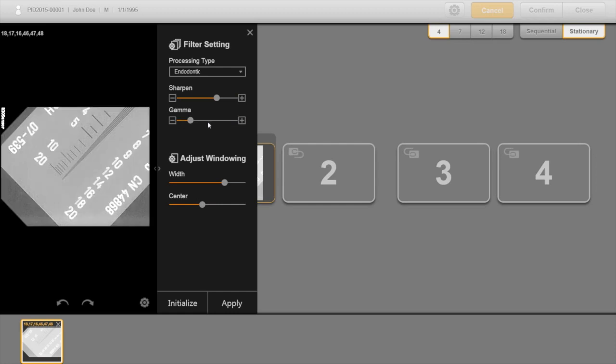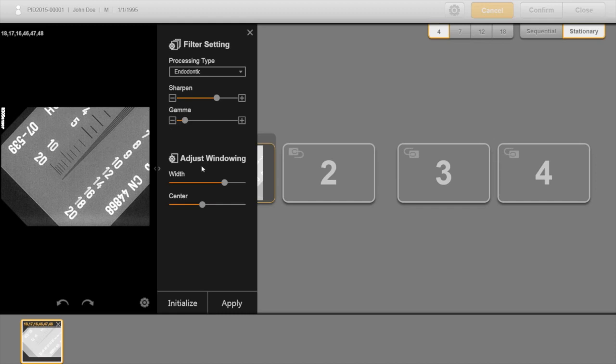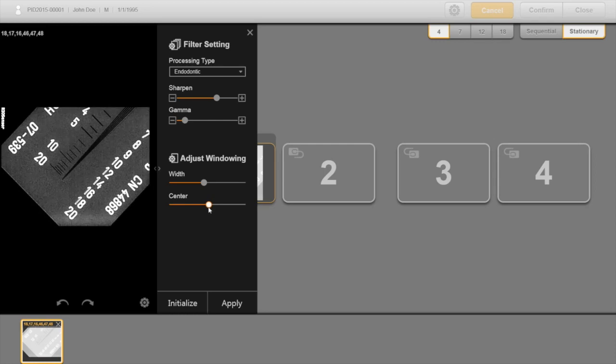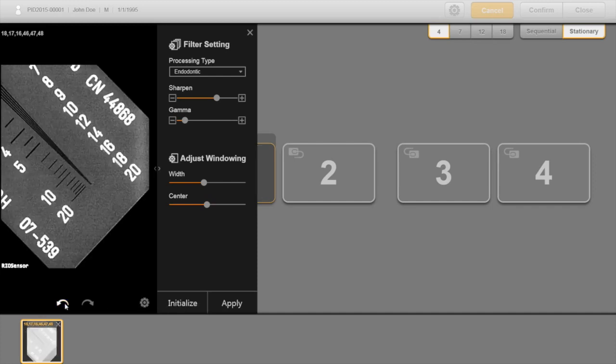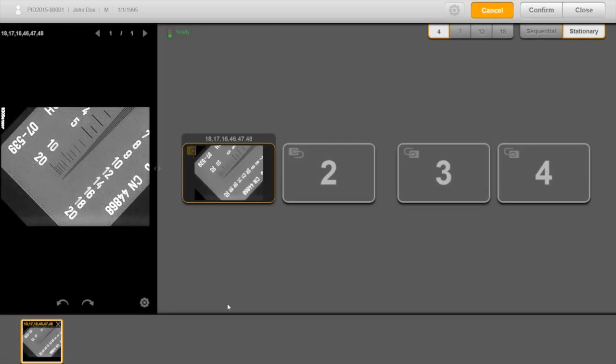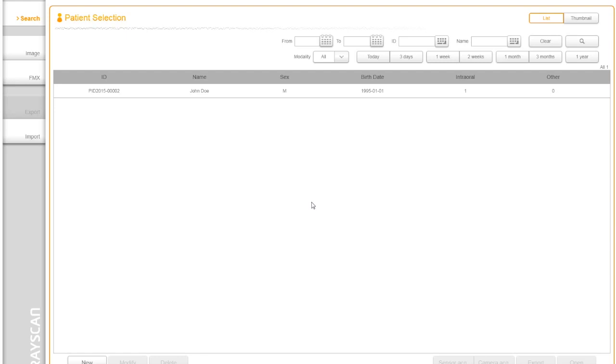The Gamma button is similar to standard brightness adjustment but is a more powerful enhancement. Gamma dynamically changes image pixels so that there is always a relative brightness difference between them. This ensures the changes in density within the image will be maintained, as opposed to all pixels becoming white or black. You can also rotate the image to the left and right. To reset the filter back to its original setting, click on the Initialize button. Note, the adjustments can be modified anytime needed before saving the final images.